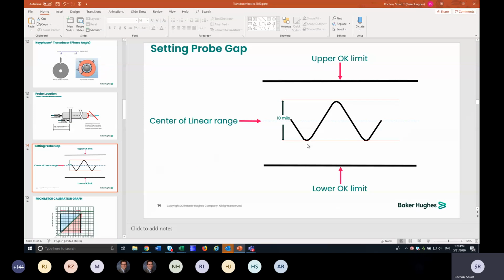One of the things that I quite often get asked is about the gapping of proximity probes. Customers will call up and go, hey, I've got this machine that the probes are gapped perfectly at -10 volts right in the center of the linear range, and I've got this other machine over here that's gapped at -6 volts. Is that throwing my vibration reading off? And the answer to that is no, not unless your vibration reading is massive.